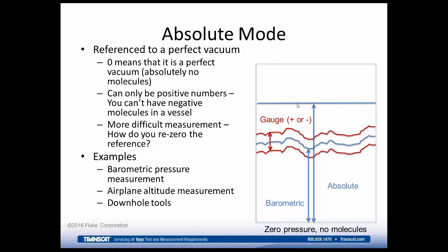Absolute pressure can be a more difficult measurement, but an extremely useful measurement. And the challenge that makes it a more difficult measurement is re-zeroing the measurement device, re-zeroing the reference. What we mean by that is that just about every pressure measurement device will suffer from what we call zero drift. That is that over time, the reading of the device will drift, where it will have an offset throughout its entire range. And this is what we would call zero drift.